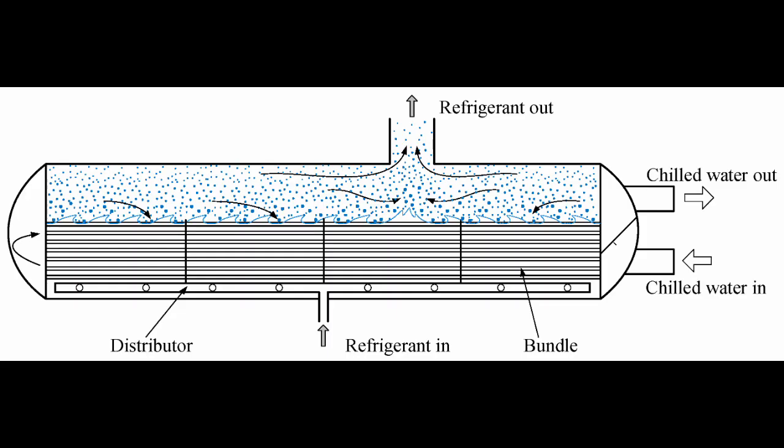Flooded type coolers. Parts used in a flooded type cooler and their functions are as follows: one, shell — where refrigerant flows; two, tubes — where water flows. In a flooded type cooler, refrigerant enters from the bottom of the cooler and exits from the top, while water enters from the side and exits from the other side, if it is a single pass type cooler.